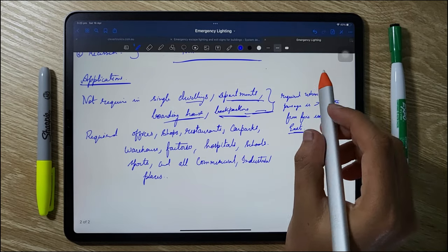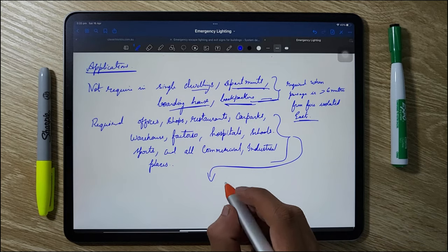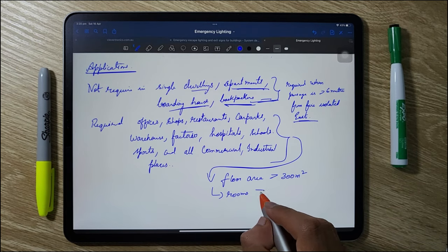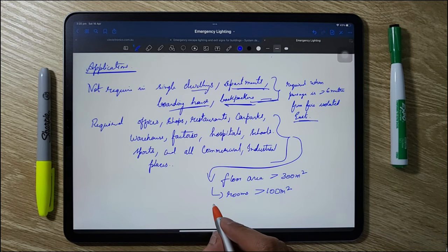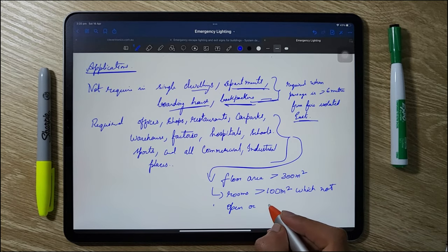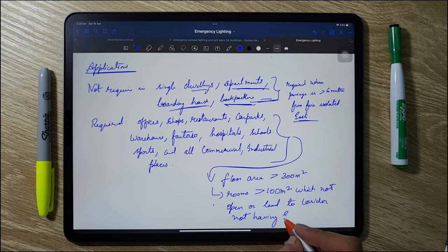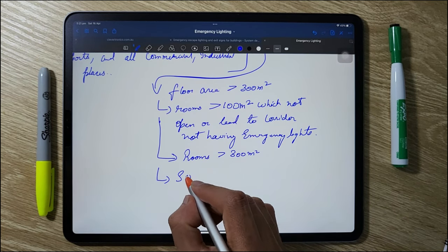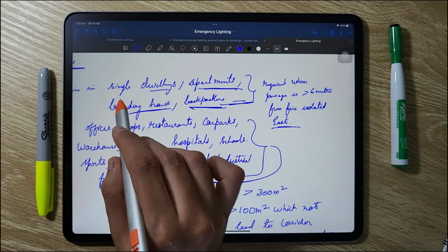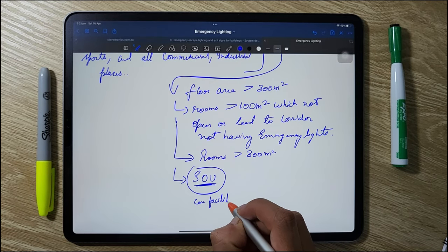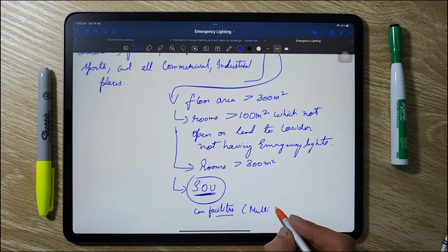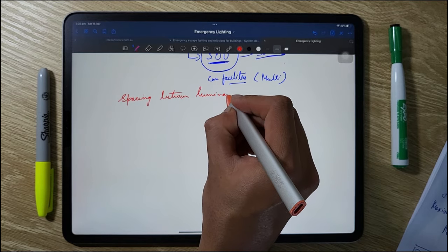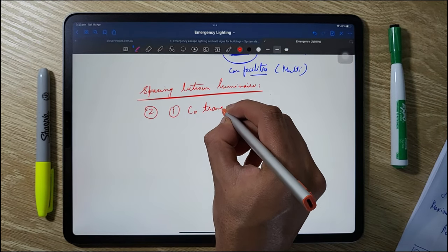For residential and commercial places like offices, shops, restaurants, and car parks, emergency lighting is required in every building with a floor area over 300 square meters. Every passageway, corridor, and hallway should have emergency exit signs and emergency lighting. Any room larger than 100 square meters that does not open to a corridor with emergency lighting also needs emergency lighting. Any room larger than 300 square meters must be provided with emergency lighting. Sole occupancy units greater than 300 square meters in commercial buildings also need exit signs and emergency lights.